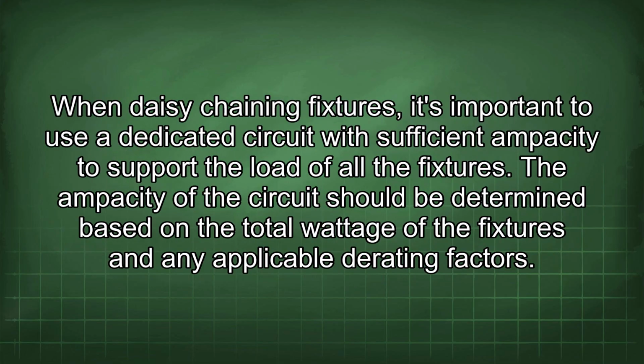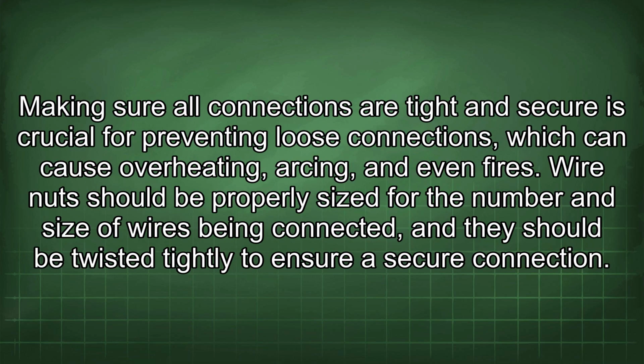When daisy chaining fixtures, it's important to use a dedicated circuit with sufficient ampacity to support the load of all the fixtures. The ampacity of the circuit should be determined based on the total wattage of the fixtures and any applicable derating factors. Making sure all connections are tight and secure is crucial for preventing loose connections, which can cause overheating, arcing, and even fires.